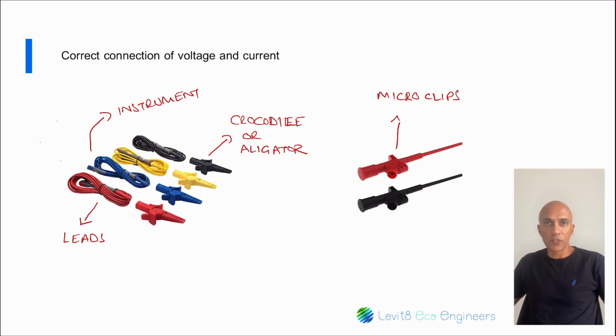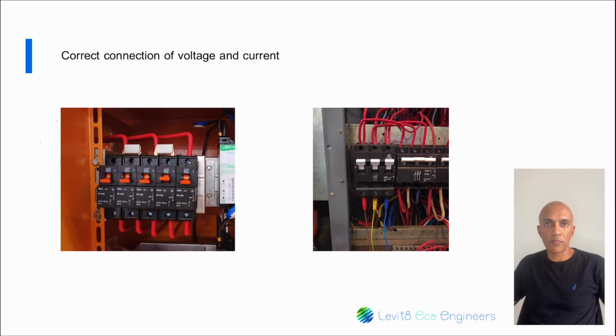Now, if you have a look at this photo, this example shows the type of point that you could connect the micro clips to. These types of connection points are rare, but you should get the idea. If you have a look at this photo, you've got these little exposed bus bar sections. Now, a standard crocodile or alligator clip is not going to go around there. So you could use a micro clip to connect there, or let's assume this feeder here has got a little bit of exposed insulation, then you could connect onto there. But before you do any connections, make sure that these terminals are tight so that your wire does not come out and cause a loss of supply on one of the circuits.